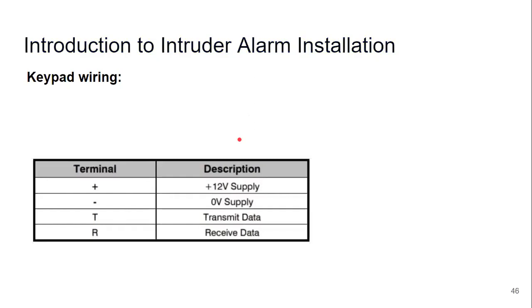Now for keypad wiring: you can buy a Honeywell PIR and connect it to a Texecom, Pyronix, or Honeywell system — it doesn't matter, because PIRs work by circuitry and can connect to any system. However, for keypads — anything that makes data communication — it has to be the same brand. If it's a Honeywell system, it's got to be a Honeywell keypad; if it's Texecom, it's got to be Texecom.